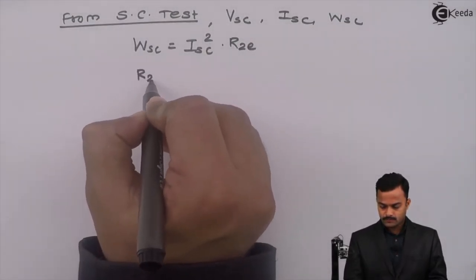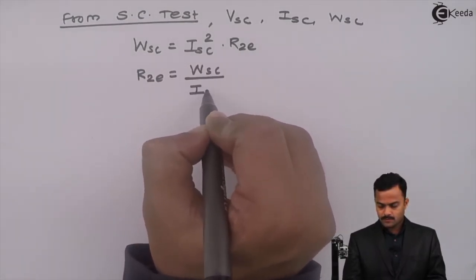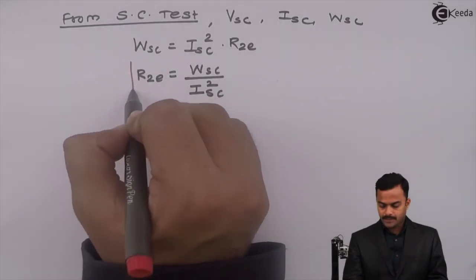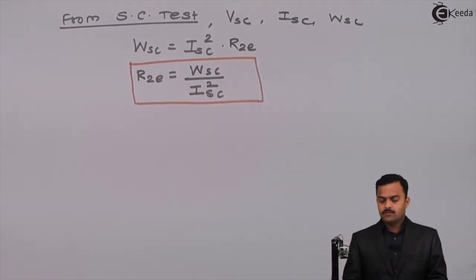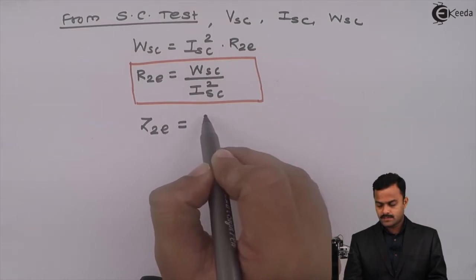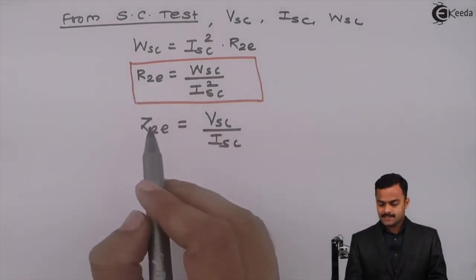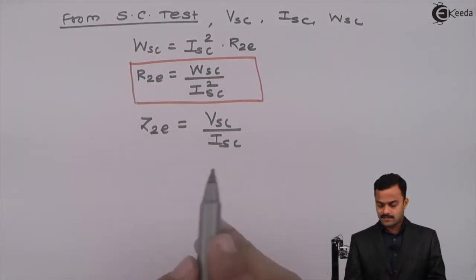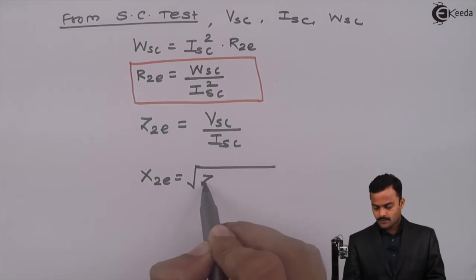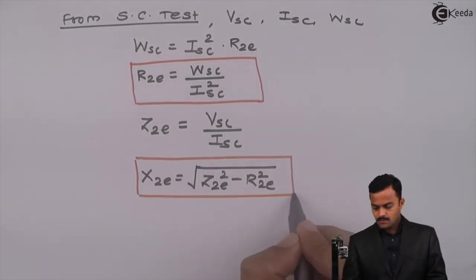From this I can get R2E equal to WSC divided by ISC². Voltage and current are known, so I can get impedance Z2E equal to VSC divided by ISC. From resistance and impedance I can get reactance: X2E equals the square root of Z² minus R².